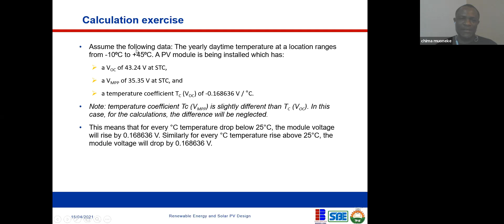So now your VOC at -10 is equal to the VOC voltage that you are given, plus 25 degrees centigrade minus -10, times your temperature coefficient for voltage. When you do this computation, you're going to get 49.14. Now, this is your open circuit voltage, the highest voltage you can get. And at this voltage, your current is 0.